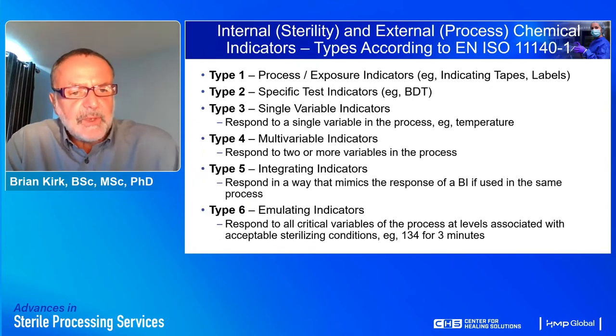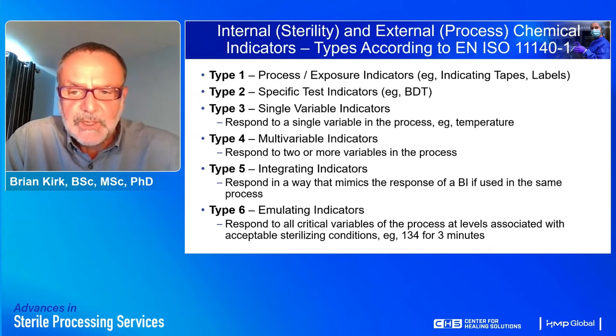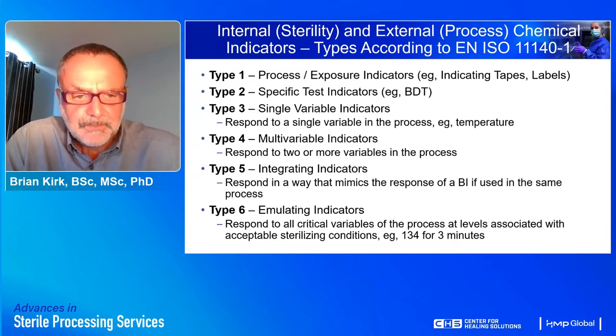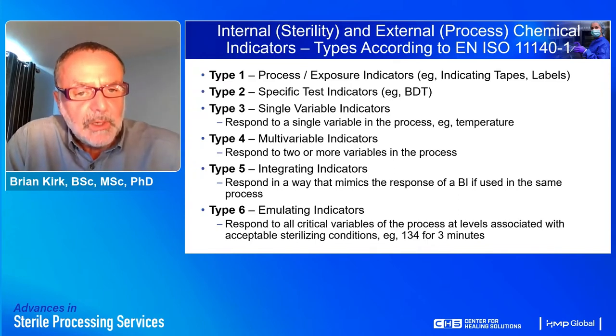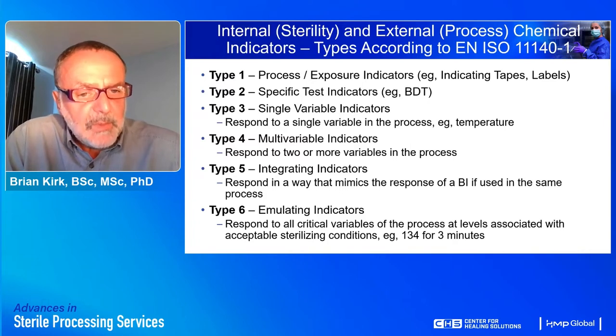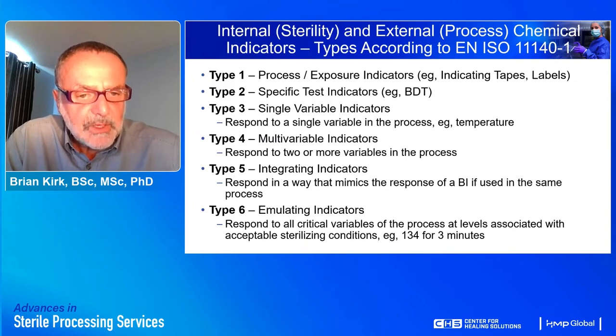There are three further categories — types 4, 5, and 6 — categorized according to performance specification. Multiple variable indicators (type 4) respond to two or more variables in the process. Integrating indicators (type 5) respond in a way that mimics the response of a biological indicator. Emulating indicators (type 6) are designed to monitor and give a pass or fail response to a very specific combination of exposure conditions.